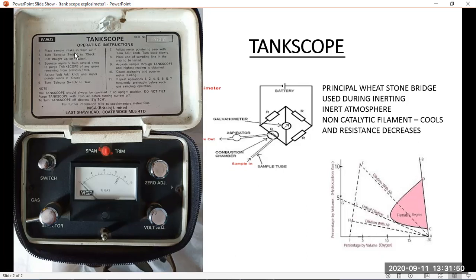So we place the sample in the fresh air. Initially we start in the fresh air, and then we turn the selector switch to the check mode. Then this switch we pull up and squeeze the aspirator bulb for taking in the gas, and adjust the voltage adjustment until the meter points the reading at check. So we adjust the voltmeter up to the check position. That is your voltmeter adjustment.